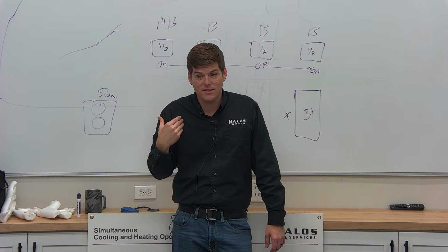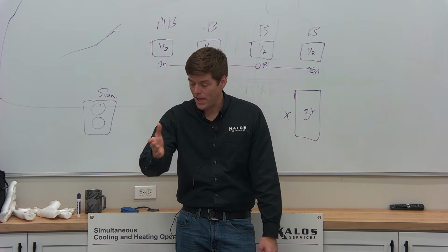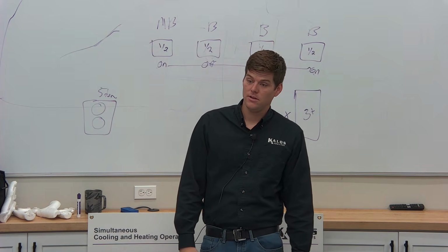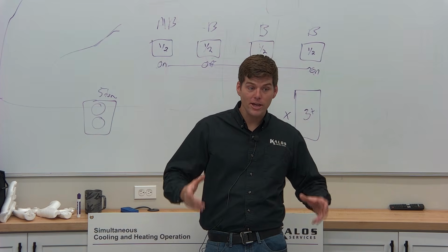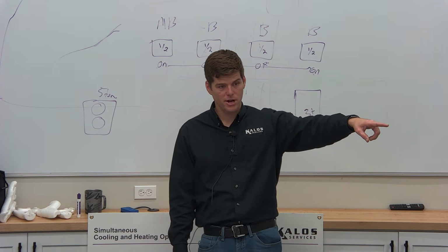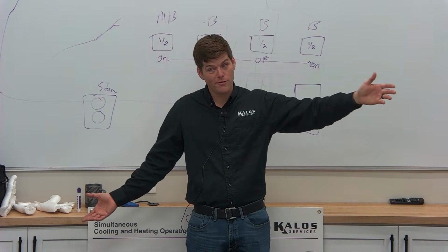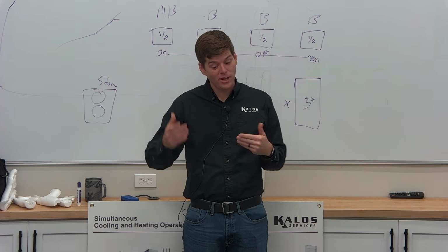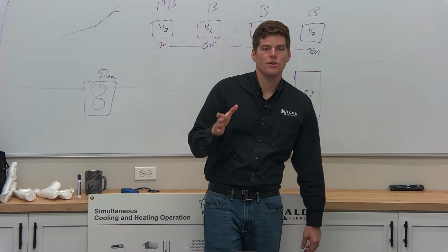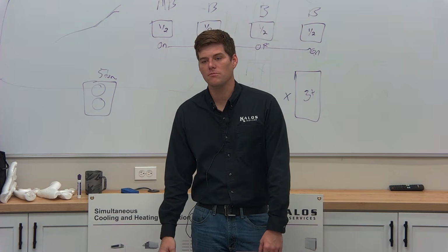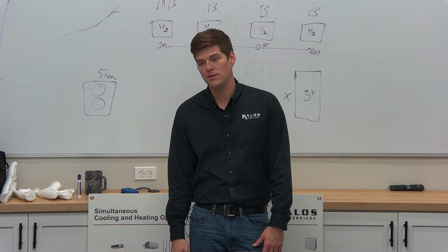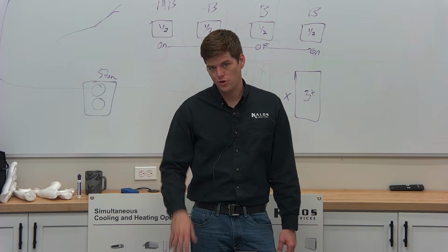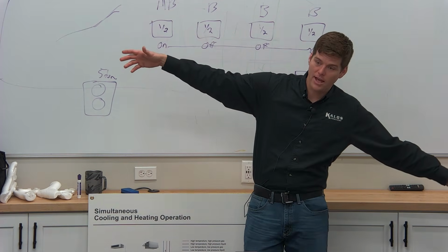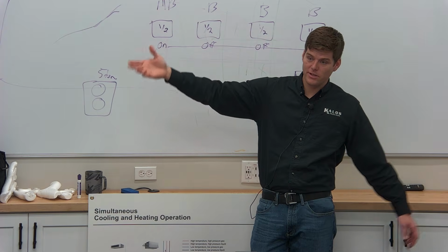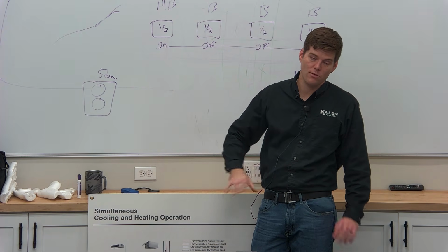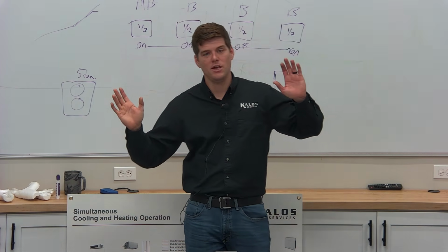Are they flared into the boxes? There are some manufacturers that do flares at boxes. All indoor units for VRF are flared connections except for the vertical fan coil, which is brazed. So you can't get away from it. You have to flare every single indoor unit. So flaring is important. When you go to leak check a VRF system, typically you want to start at the indoor units and work your way to the outside. That's just because Joe Schmo took that 100-foot roll that he had and spooled it above the ceiling and never actually redid the flares on the mechanical press fittings that come from the factory. Don't worry, I've done it a million times, so no judgment here.